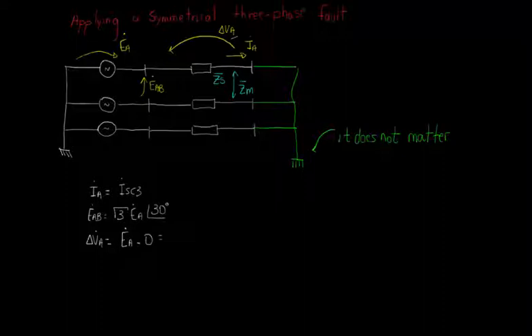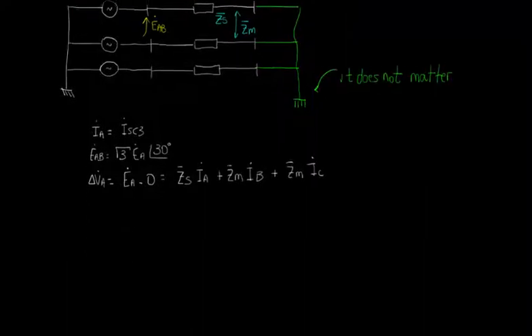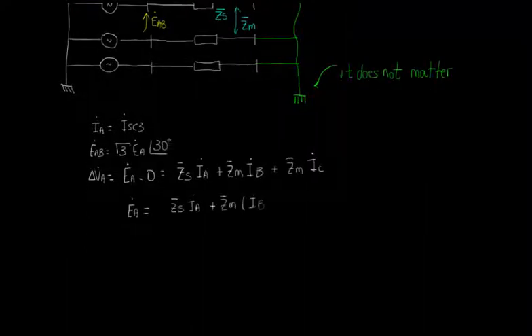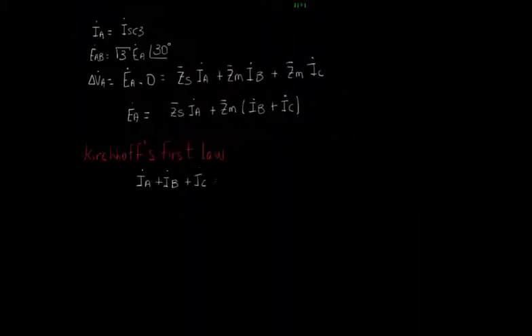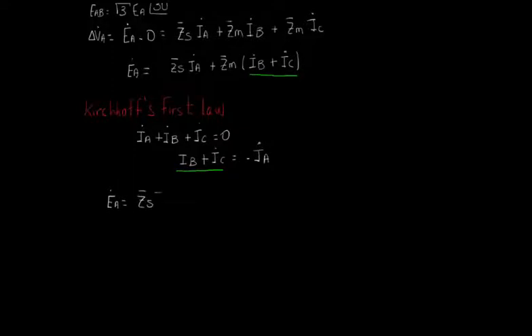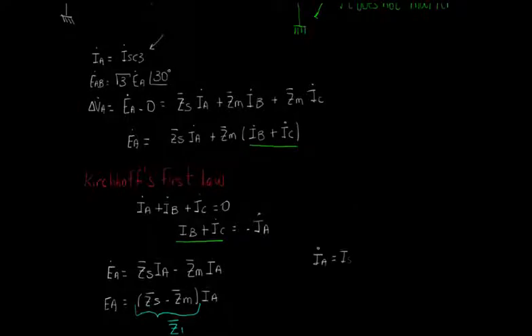Applying KVL in phase A, we get that delta VA is equal to ZS times IA plus ZM times IB plus ZM times IC. Putting ZM in evidence, we can write this equation here. Now, applying KCL in the fault node, we get that IA plus IB plus IC is equal to 0, and by consequence, that IB plus IC is equal to minus IA. Substituting it in the first equation, we can find that EA is equal to ZS minus ZM times IA, and you have already seen that ZS minus ZM is the positive sequence impedance Z1.